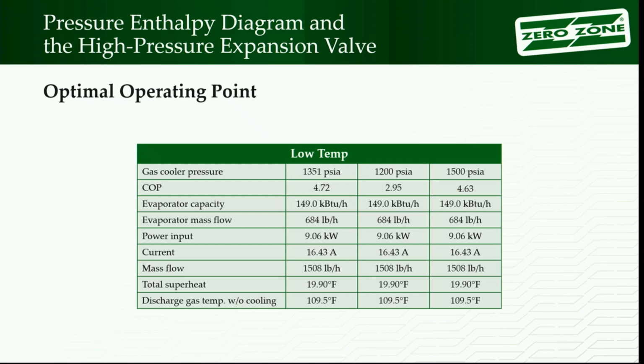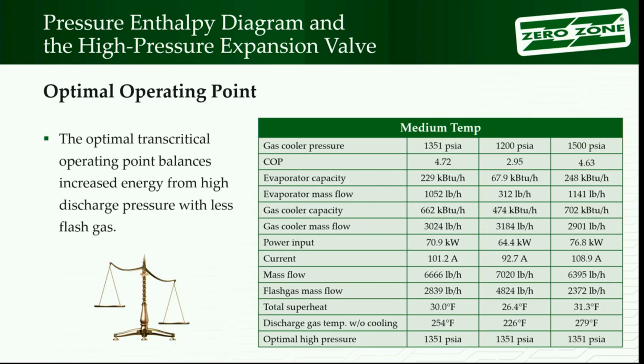The flash tank pressure doesn't change, the temperature doesn't change, that compressor just keeps chugging along. Nothing's changed for it. That discharge pressure hasn't moved. Compressor's sort of isolated, maybe that is too strong of a word, but that's sort of what it is. It's sort of separated out of the system. High side of the system, whole different ball game here.